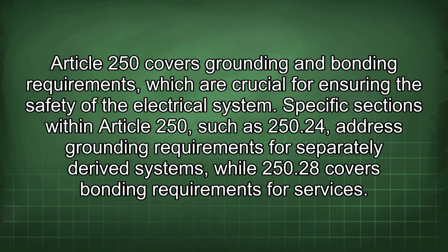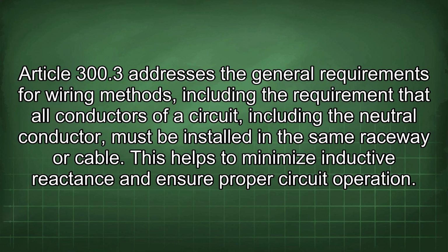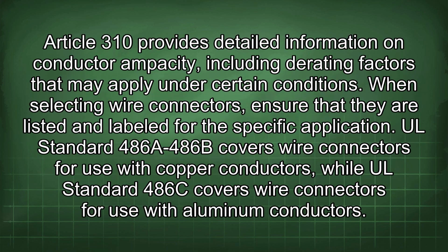for services. Article 300.3 addresses the general requirements for wiring methods, including the requirement that all conductors of a circuit, including the neutral conductor, must be installed in the same raceway or cable. This helps to minimize inductive reactance and ensure proper circuit operation. Article 310 provides detailed information on conductor ampacity, including derating factors that may apply under certain conditions. When selecting wire connectors, ensure that they are listed and labeled for the specific application.